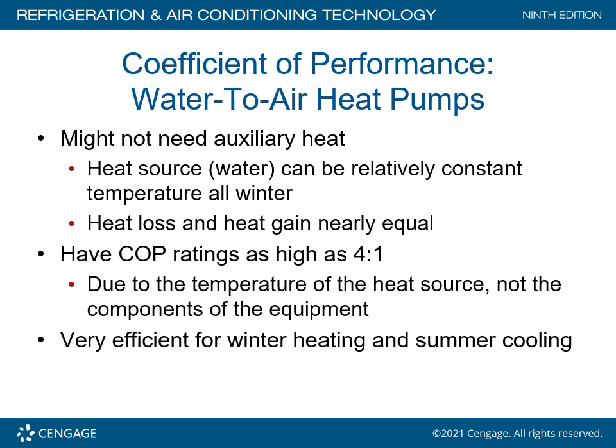Okay, in this slide here we have coefficient of performance. Water-to-air heat pumps might not need auxiliary heat. A water source can be utilized, which is relatively constant in temperature all winter. Heat loss and heat gain are nearly equal. The COP rating, coefficient of performance rating, is as high as 4:1, due to the temperature of the heat source, not the components of the equipment. Very efficient for winter heating and summer cooling. The key is to keep that water temperature consistent. We'll talk about that in the next chapter.